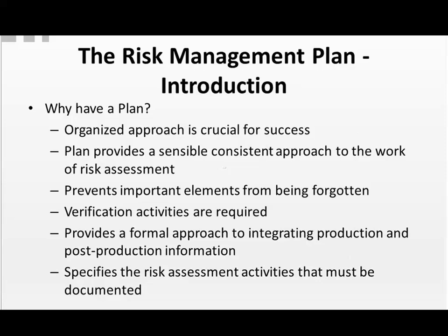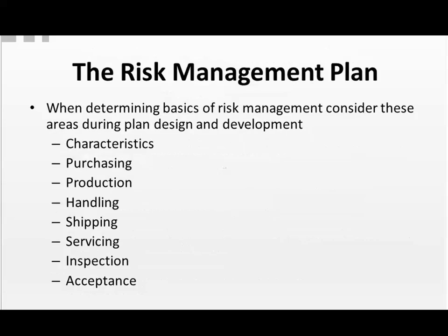Verification activities are required, but often don't happen without a plan. The plan provides a formal approach to integrating production and post-production information into risk management. And the plan specifies the risk assessment activities that must be documented and housed in what we call the risk management file.